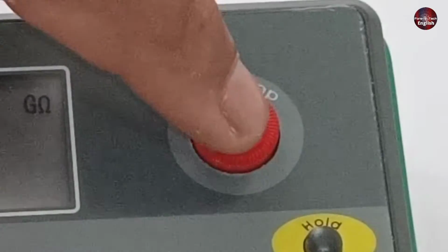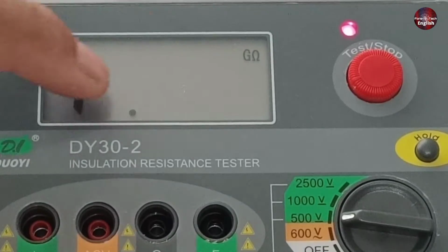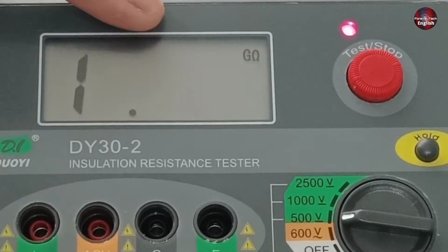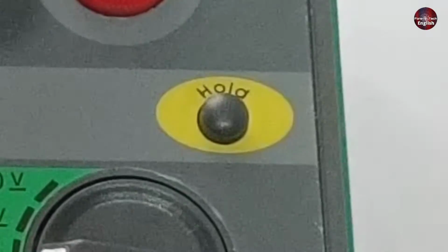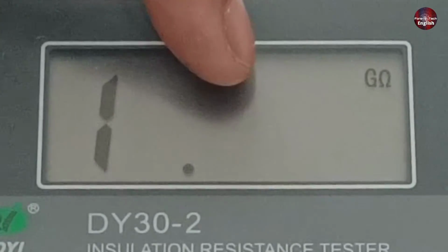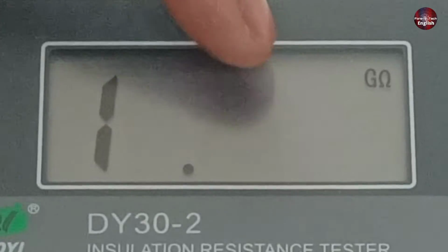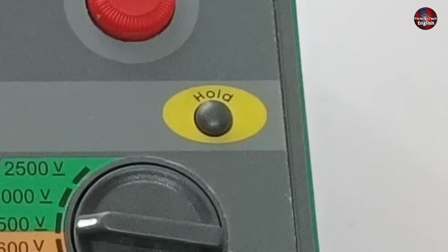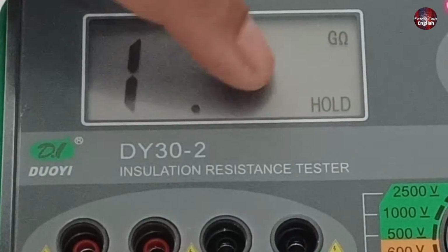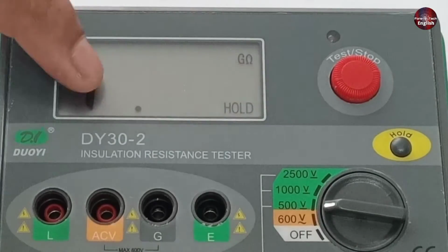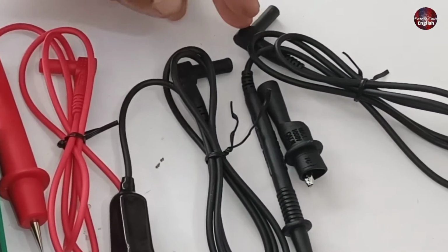I will press the test and stop button. The megger will start testing the device attached to it. A hold button is present in the megger. The reading is shown on the display of the megger, and if we want the reading to stay on the megger, then I will press the hold button, and the reading will stay on display even after pressing the stop button. This megger has 3 types of cables.